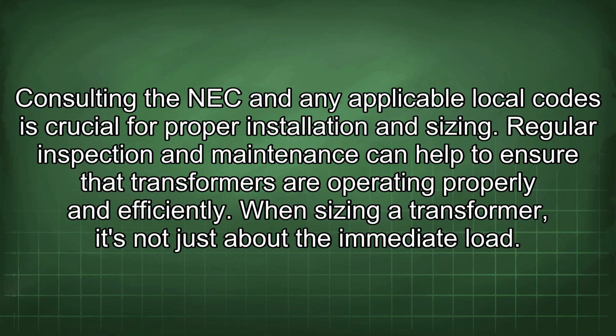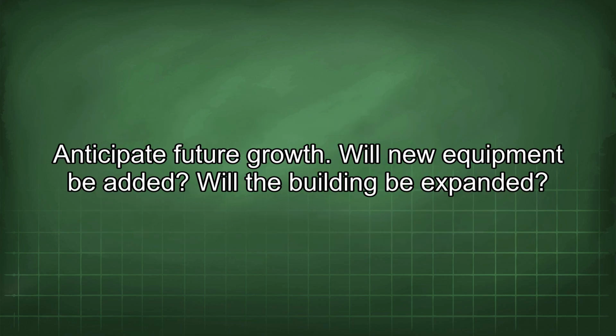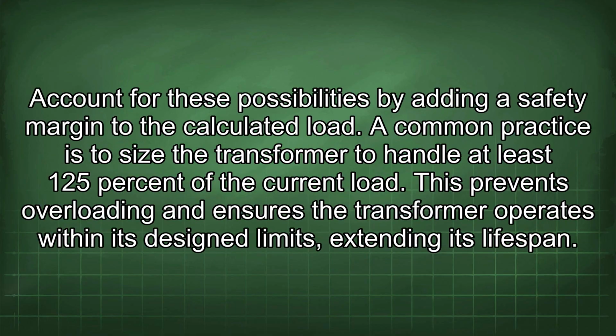When sizing a transformer, it's not just about the immediate load. Anticipate future growth. Will new equipment be added? Will the building be expanded? Account for these possibilities by adding a safety margin to the calculated load. A common practice is to size the transformer to handle at least 125% of the current load. This prevents overloading and ensures the transformer operates within its design limits, extending its lifespan.